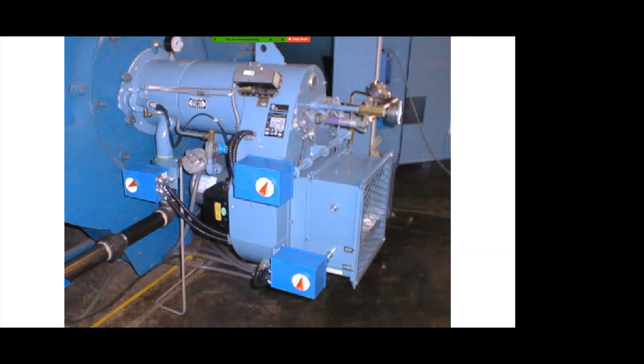Yeah, that's a good point right there, Jeff. With that linkage, when Jeff says things go off ratio, for natural gas, we try to get perfect combustion. They say 10 to 1. That's 10 air molecules to 1 gas molecule. And with the Control Links system, it allows you to basically maintain that 10 to 1 ratio all the way through from a low fire to a high fire condition. And what happens when you have linkages, like Jeff said, you have a lot of slop in the linkages. Every little connection you put, the shafts, they have little slop.